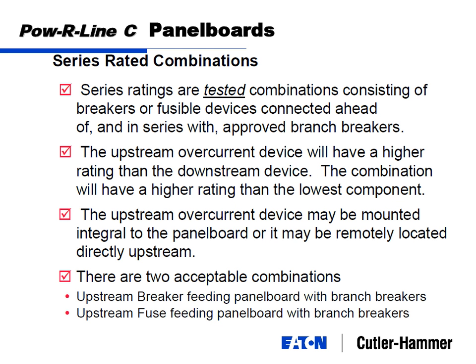Okay, so series ratings, just to summarize these points, are tested combinations consisting of breakers or fusible devices. We can have a fuse upstream and feeder breakers downstream. Upstream device will have a higher rating than the downstream device. The combination is the series rating. So a combination rating is what they call the series ratings, and those are all published.